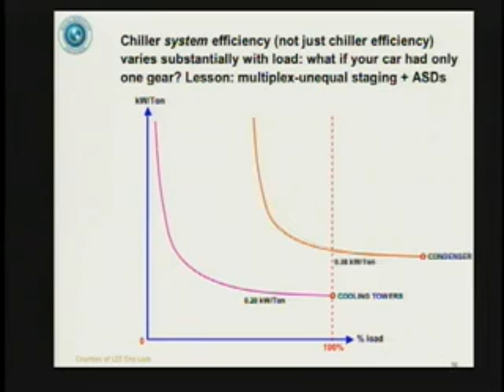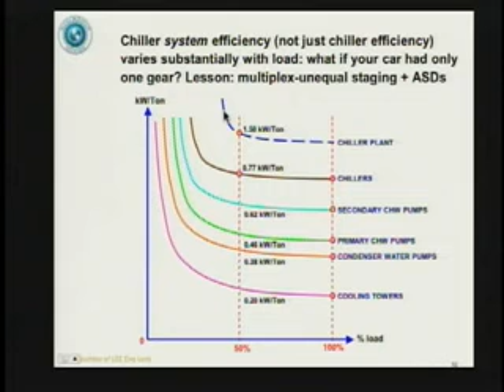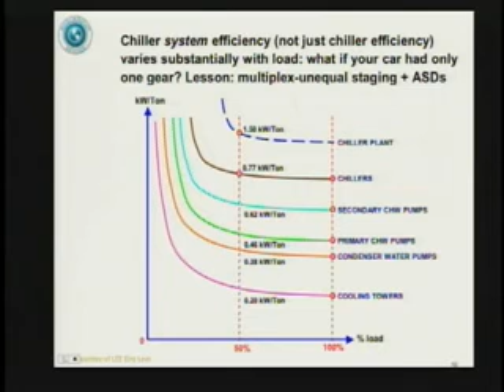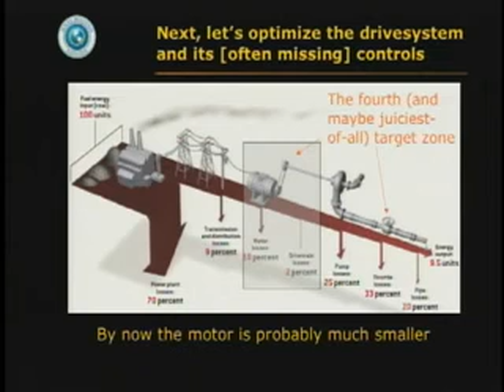Then you need to think about how the pumping efficiency affects, say, a whole cooling system. You've got cooling towers and condenser water pumps and so on that, as you go toward low load, get extremely energy intensive and inefficient. Primary chilled water pumps, secondary, if you have them, chilled water pumps, chillers themselves. And by the time you get through, your whole chiller plant is very inefficient. If it goes below about half load, which it probably will most of the time because it's so oversized, then it's really inefficient. It's like trying to drive efficiently a car that has only 1 gear instead of 5. So again, multiple different size pumps, adjustable speed drive.